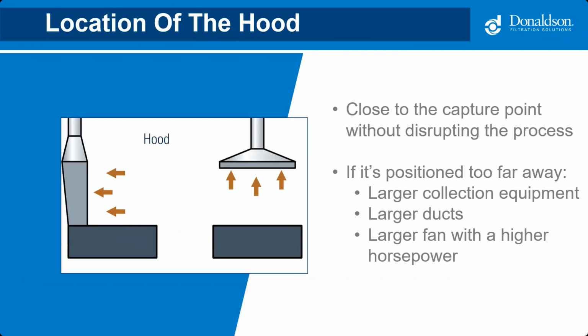So to minimize the air volume, the hood must be close to the capture point without disrupting the process. We have to remember, we only want the fugitive dust. We don't want to pull good product. As a general rule, a hood positioned twice the design distance from where the contaminant emission point occurs needs to draw approximately 4 times the amount of air to produce the same capture efficiency. So this is why proper design is critical, because more air means larger collection equipment, larger ductwork, larger fan with higher horsepower, all of which adds to the capital and operational costs of the system.